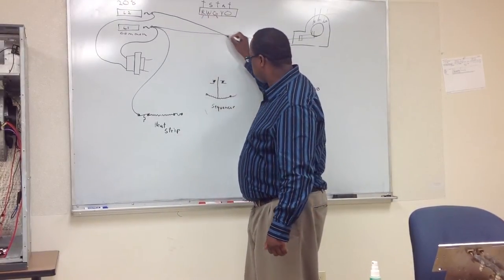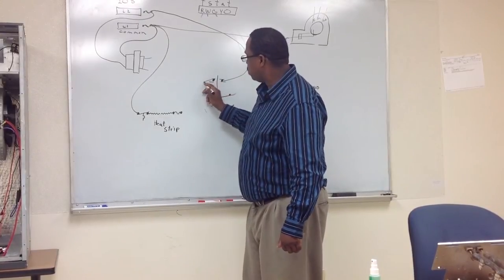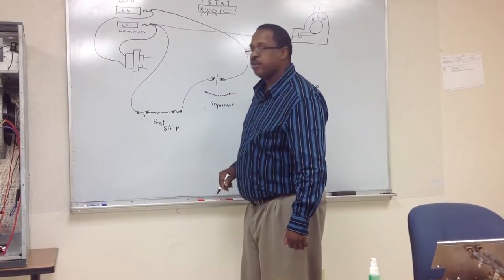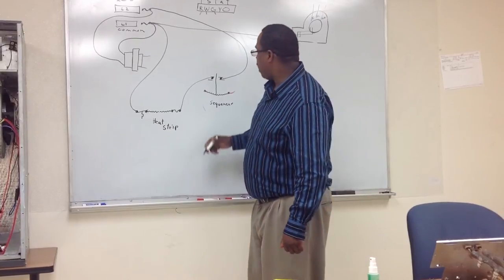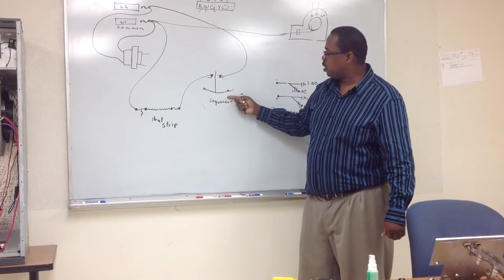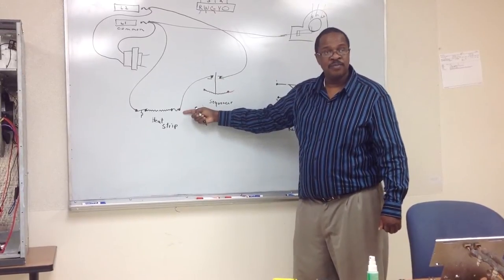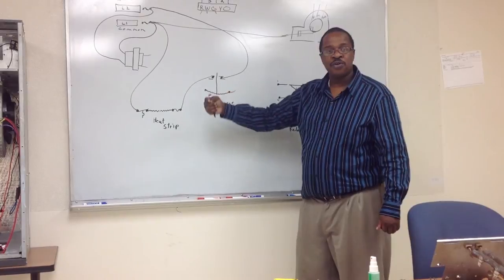Now, one leg power load, the other leg has to run through a switch. So we run L2 through the sequencer to our heat strip. Now, by means of W from the thermostat, we control the sequencer, which gives us control of the heat strip. One thing controls the next.